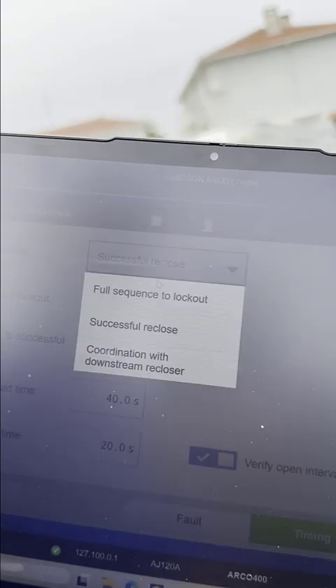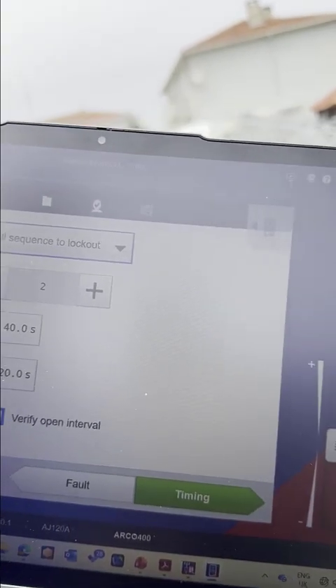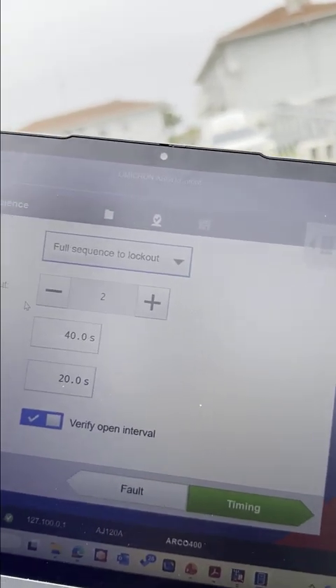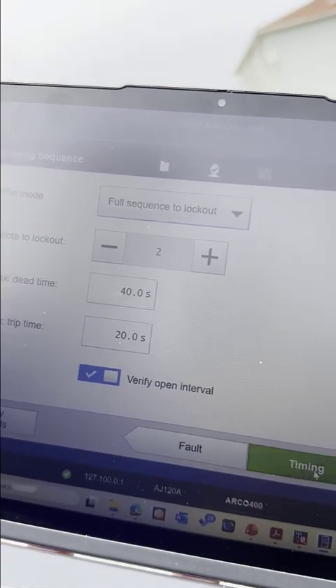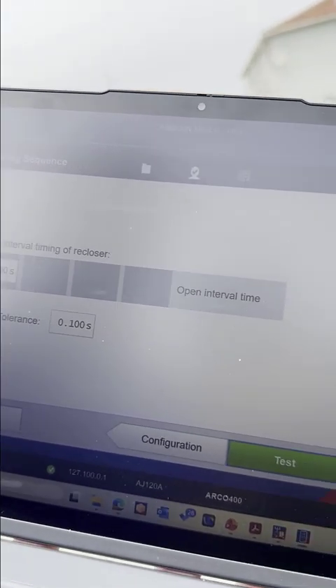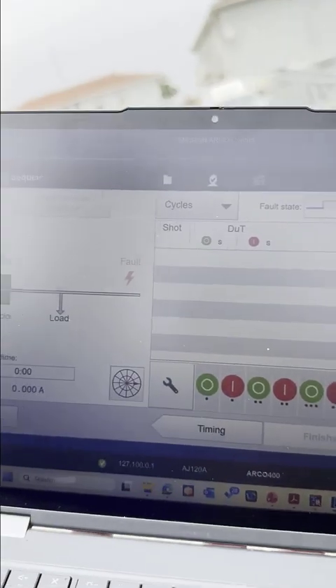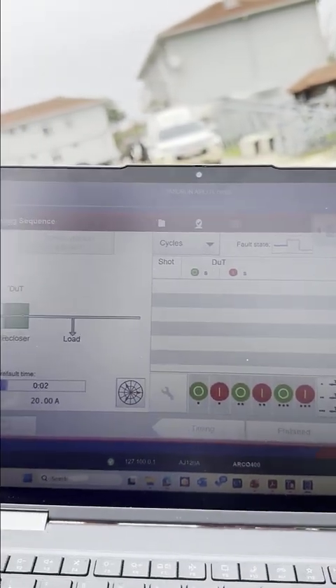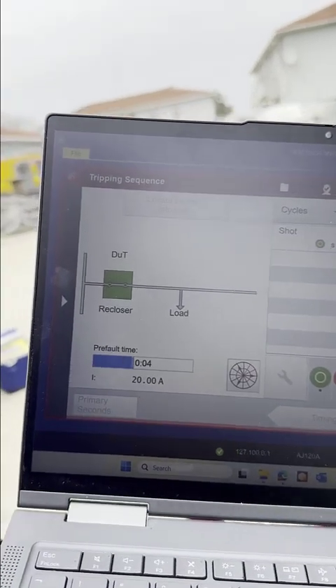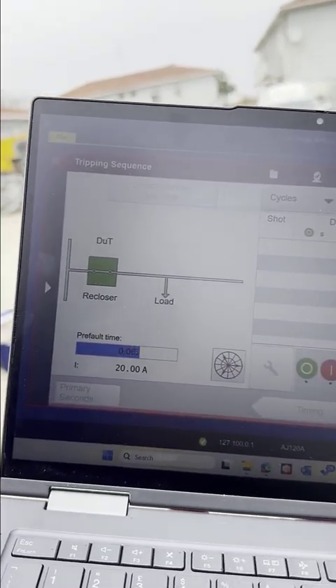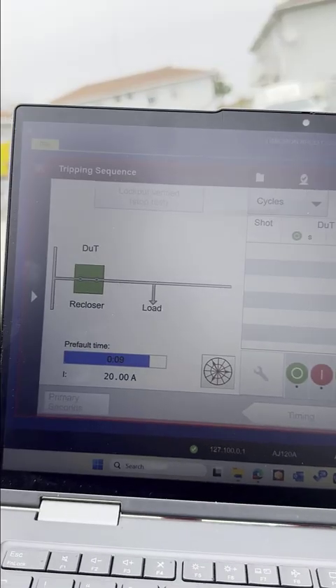Now we will select the full sequence to lockout, which means it will give a second trip after the first reclose. We will also verify the open interval, which is the dead time of the first shot, and we can select okay. We can select apply. Here is the pre-fault to simulate the load condition.